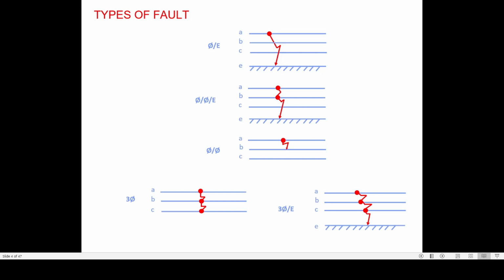The second type of fault, the shunt fault, includes a fault between one phase and ground, or between two adjacent phases, or two phases and then touching the ground, three phase or three phase to ground fault. Out of all these types of shunt faults, phase to ground faults are generally the transient faults and all other faults are persistent or permanent faults.